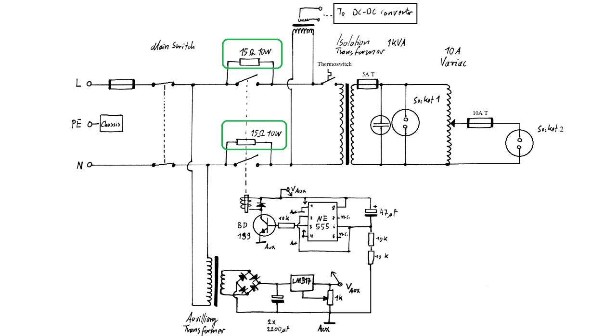At the same time, a small auxiliary transformer is directly connected to 230 volts. It doesn't require current limiting because its primary winding is made of low cross-section area magnet wire, giving it a very high wire resistance that prohibits a large inrush current surge. The secondary voltage of the auxiliary transformer is then rectified and regulated by a small linear regulator.